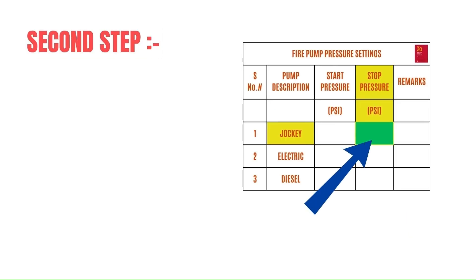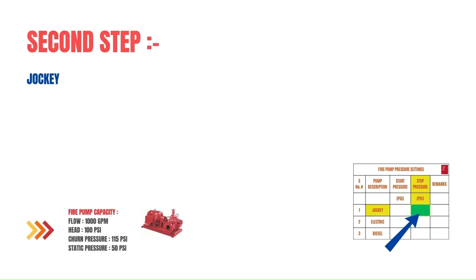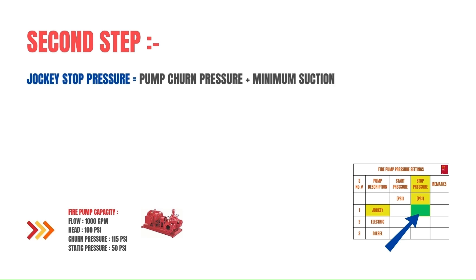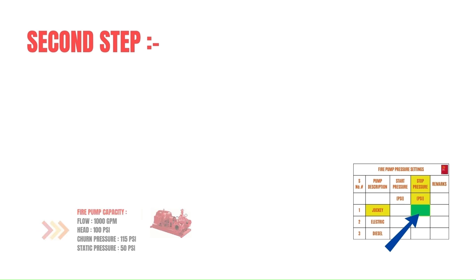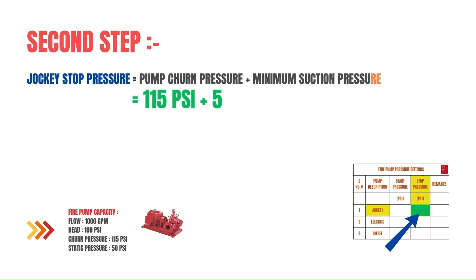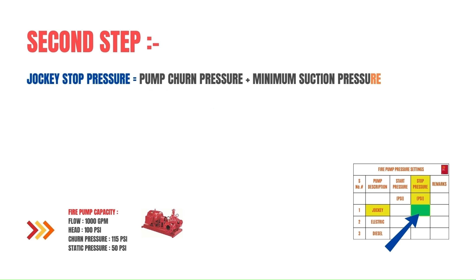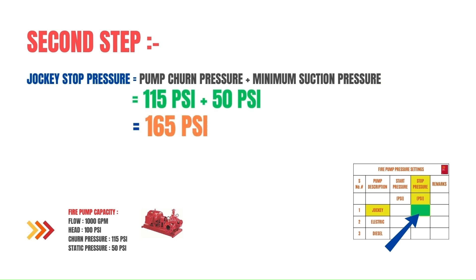Moving on to the second step, we need to determine the jockey stop pressure. The jockey stop pressure should equal the fire pump churn pressure plus the minimum static suction supply pressure. Using our data: 115 psi plus 50 psi gives us 165 psi.